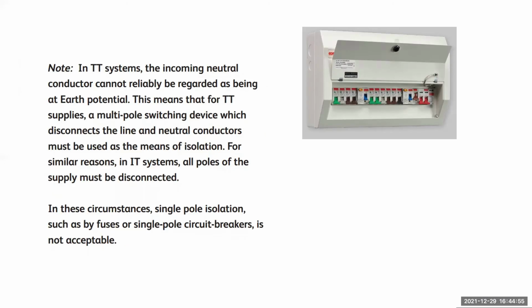It's also worth noting that the guidance from Electrical Safety First is that single pole devices are not suitable for TT systems or IT systems. Multi-pole switching devices capable of isolating line and neutral conductors should be used instead.